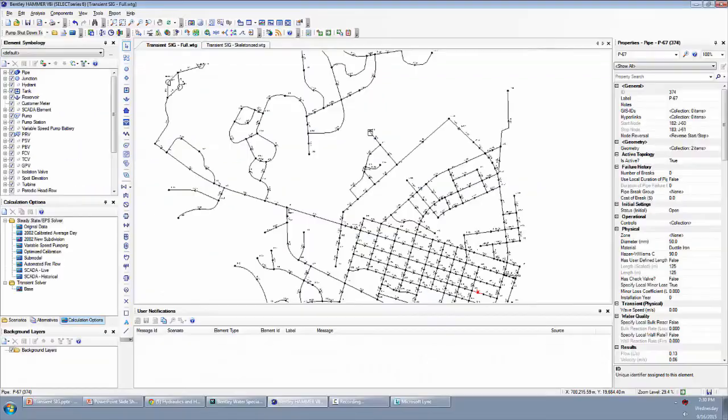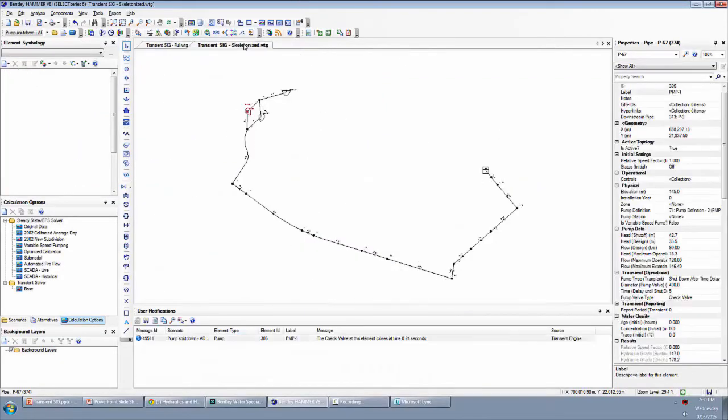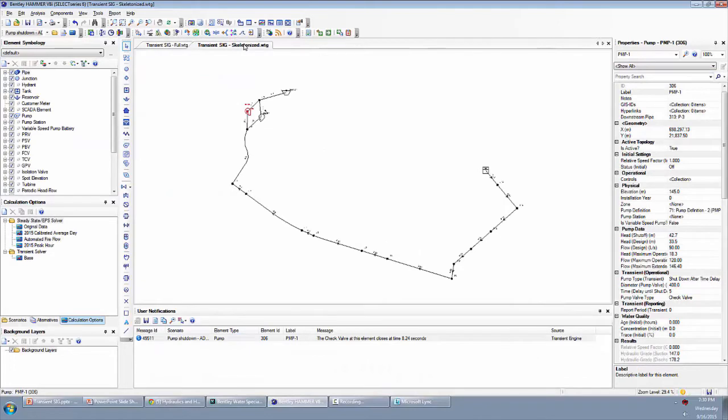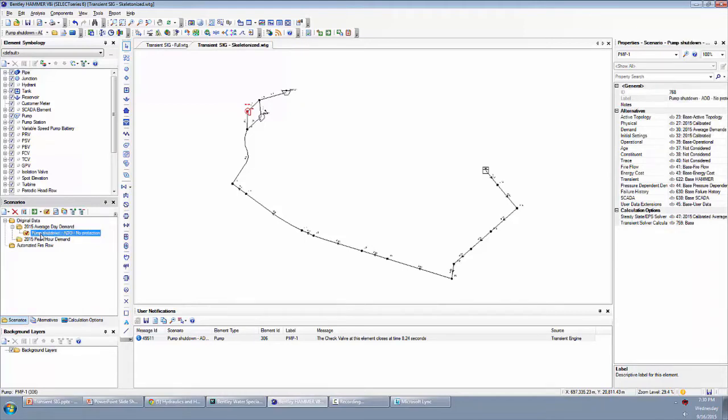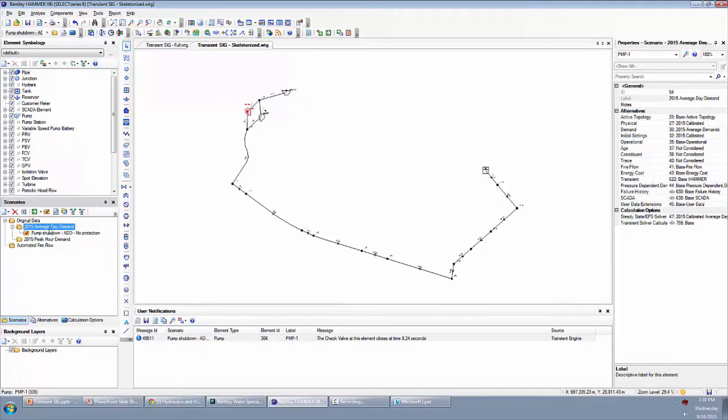So getting back to Hammer, we'll continue on with our skeletonized version here. I'll point out that when we just ran that, we actually ran a scenario that I had already created called pump shutdown average day demand, no protection. This is just a child scenario of a scenario that was already in the WaterGems model called 2015 average day demand.